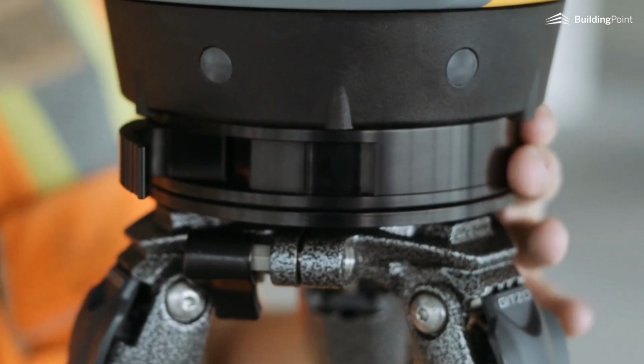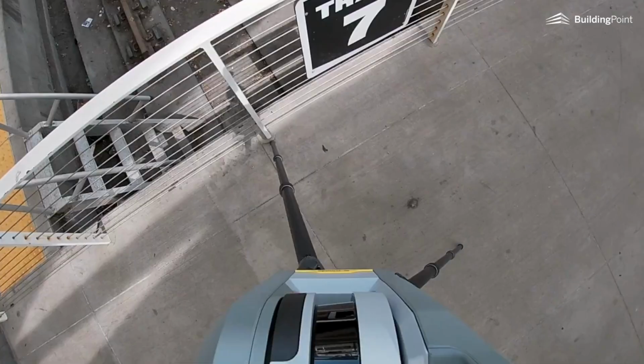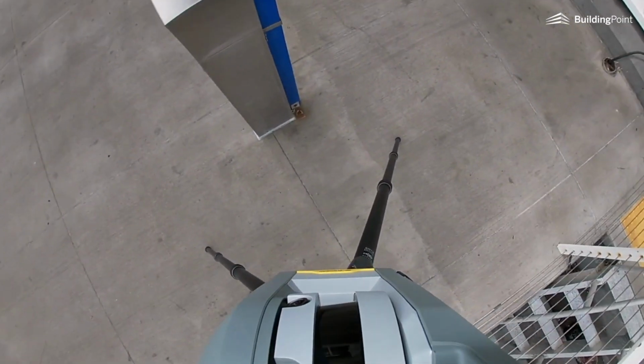Scanning is very similar in the fact we do whatever we can back in the office. Obviously, scanning is a little bit different in the fact that you're actually collecting data rather than trying to tell the equipment where to lay out.